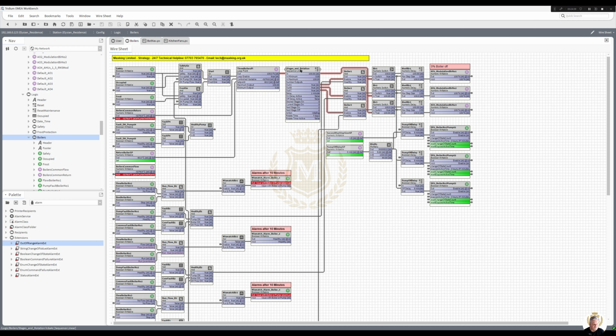Now with the loop, we're going to a sequence of linear, and I've exposed all the points. Rotation time 7 days, action rotating, and then I've got a 1 minute delay. I can change that to 5 minutes, 10 minutes, but 1 minute delay of staging up the boilers. And once we want to enable a boiler, we check the health of that boiler, pump OK, and we've got flow. So we've got the pump fault boiler 1 and the common fault boiler 1. Both of them have got to be healthy before we will enable that boiler.